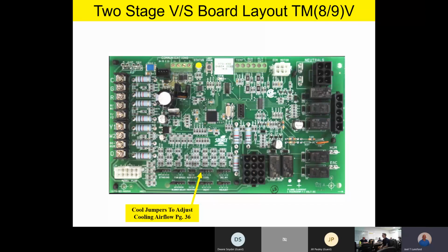So with a 2.5 ton unit outside, we set the cool and the adjust jumper up for 1,000 CFM. We look at our install information and set them up for 1,000 CFM. Now, hang on a second. We've got a two-stage unit sitting outside. We have a 19 SEER system, and we get a Y1 call on this board. The board is smart enough to know that if you're set up at 1,000 CFM and you have a Y1 call all by itself, it's going to be 65% of your high-speed cooling.